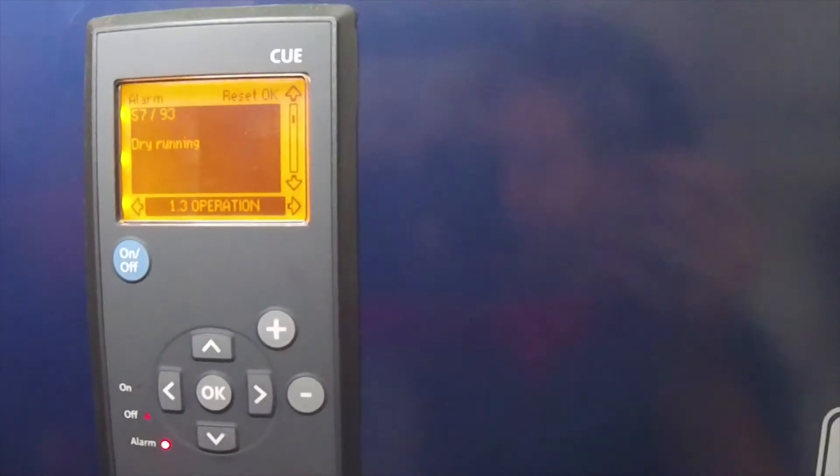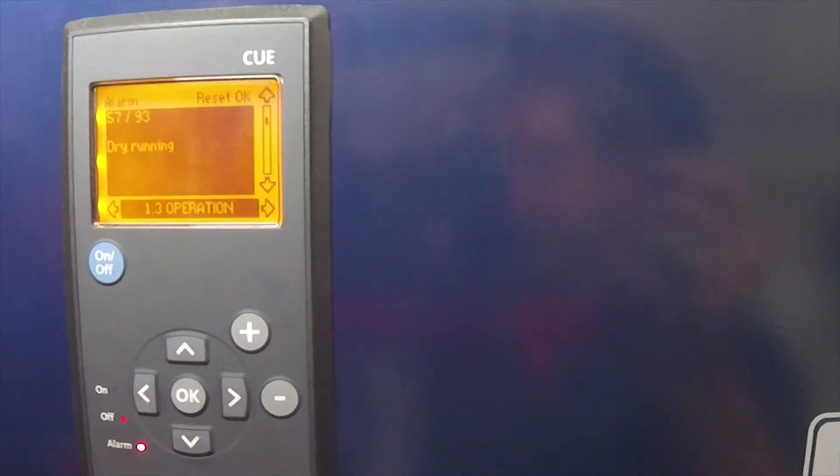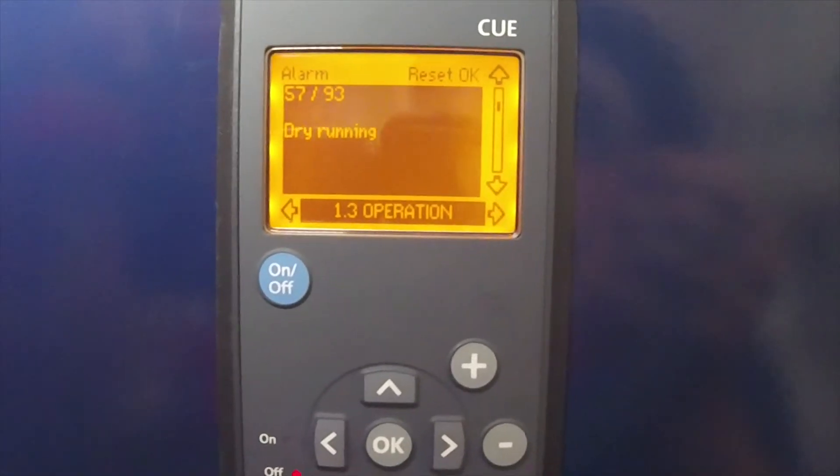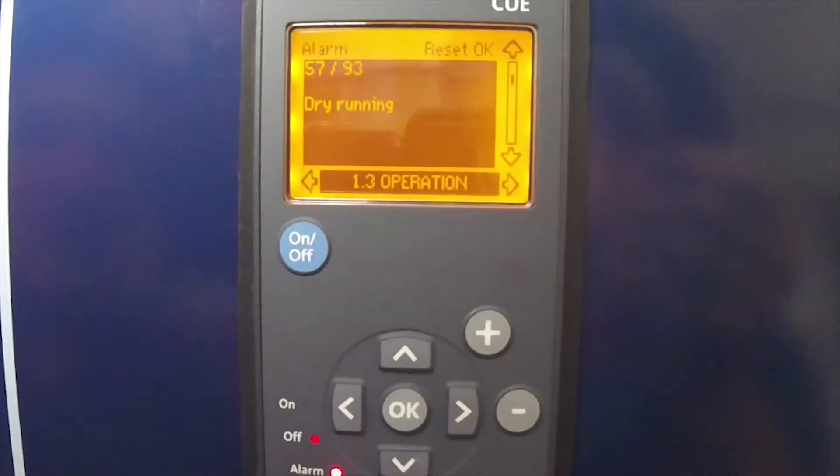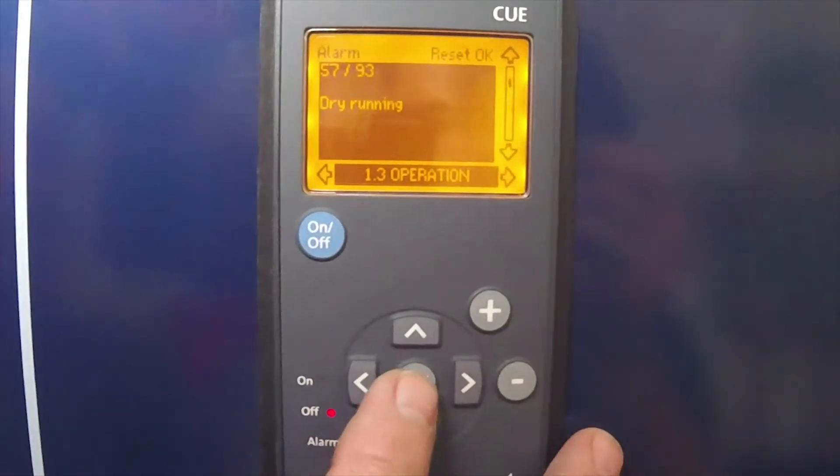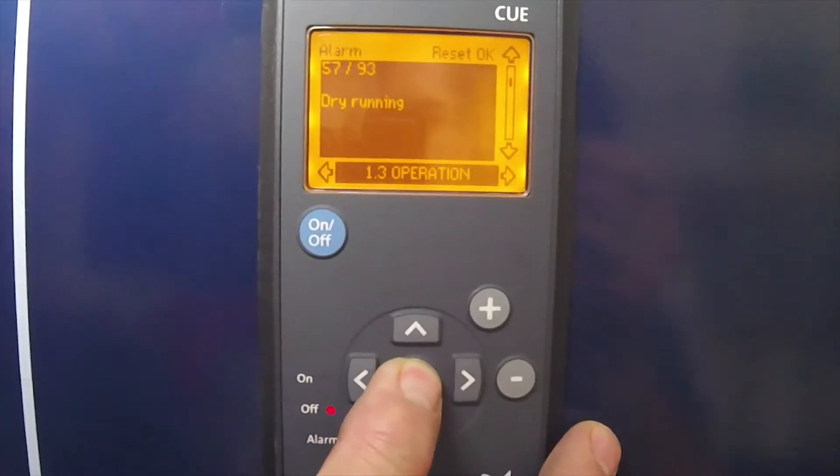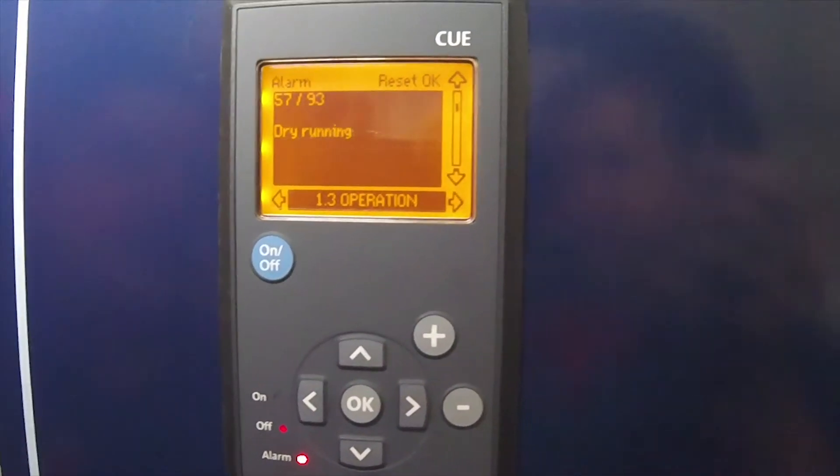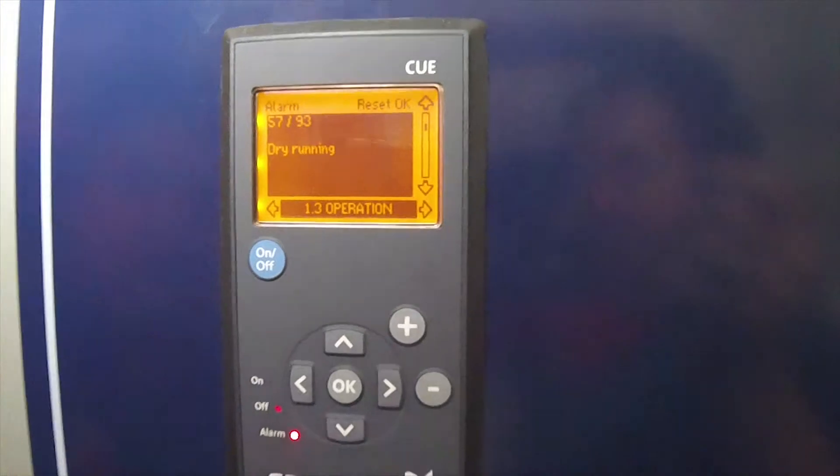It will shut the VFD down, shut the pump down, and you'll get this on the screen: dry running. And you'll notice you've got a red alarm light. To clear that, you have to hit OK.